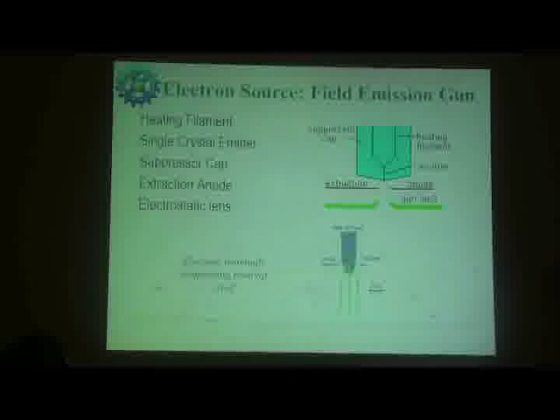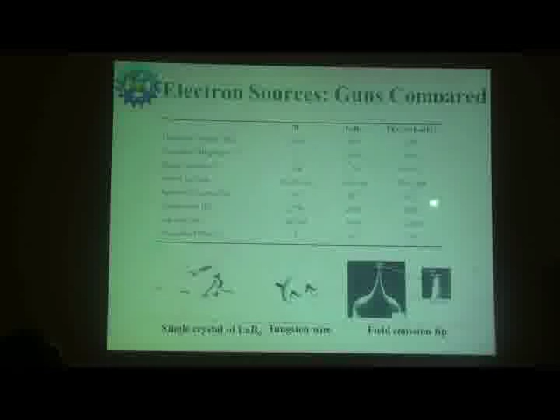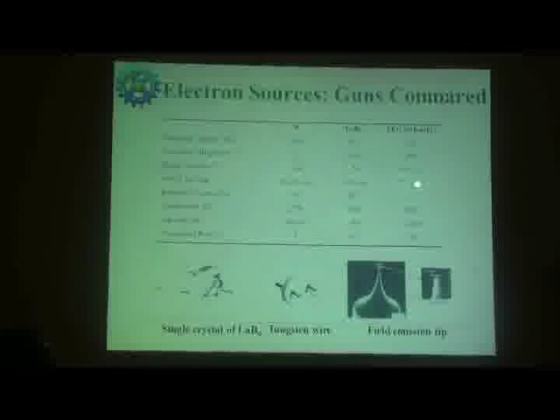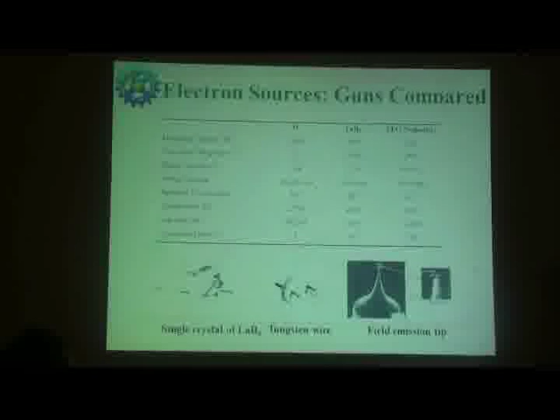When you compare the different sources, you have different parameters, starting from price, lifetime, temperature, and vacuum. If you see, the vacuum is very high when you go for field emission. In field emission we also have different sources, that is cold emission gun and Schottky emission, and what I have given is Schottky emission. So you can take the source spot size very small, compared to the source spot size of tungsten, which is very high. You can go to like 15 to 30 nanometers, so you can go for very high resolution in the case of the field emission gun. When it comes to the price, I think it is 100 times more than the tungsten filament.